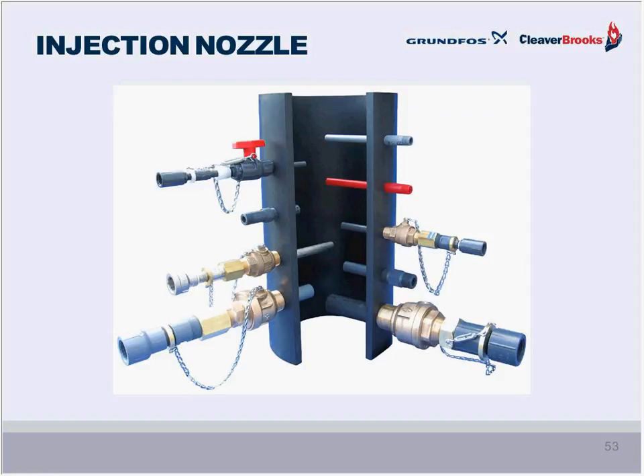A stainless steel example we saw earlier for the amine. Injection nozzles are part of the complete installation, but are typically outside the scope of a package dosing system. And this is because injections are located at the exact point where the chemical meets the process. Typically, tubing or pipe is used to transport chemical from the discharge of a dosing system to the nozzle. They vary from application to application, and this is why we leave it out of the scope of a package dosing system. We don't know that length.